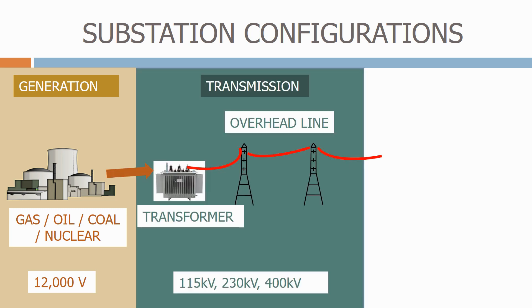We then have the transmission network, where the 12,000 volts produced by the power station is stepped up to a higher voltage using a transformer. We step up the voltage to minimise the losses on the network and increase the amount of power that can flow through it. The power is then distributed over the transmission network using overhead lines and cables. The typical transmission voltages are 115 kV, 230 kV or 400 kV.